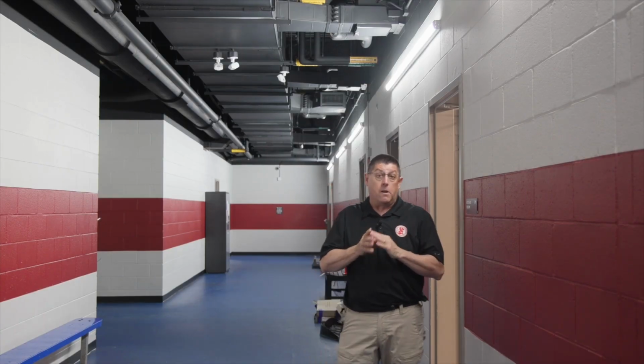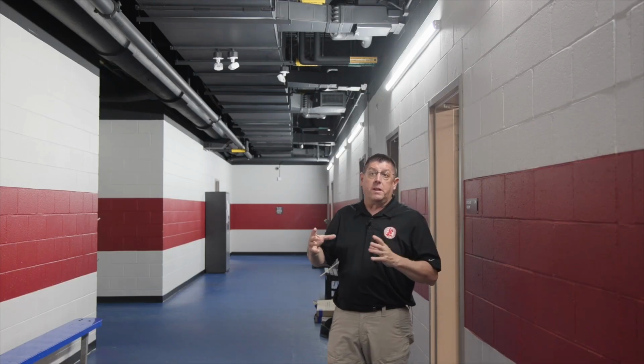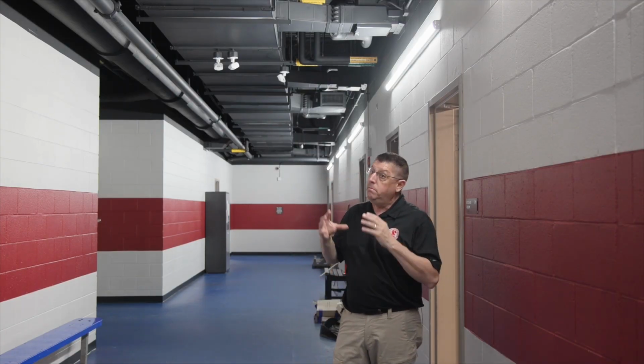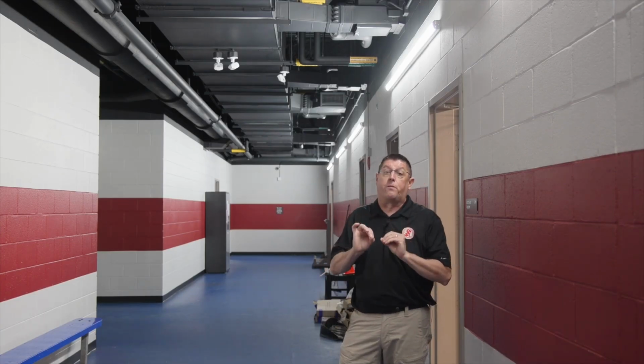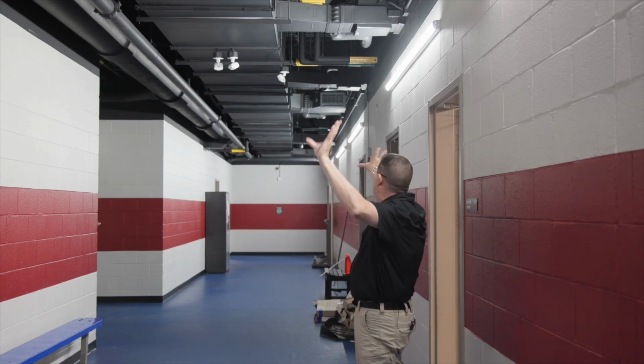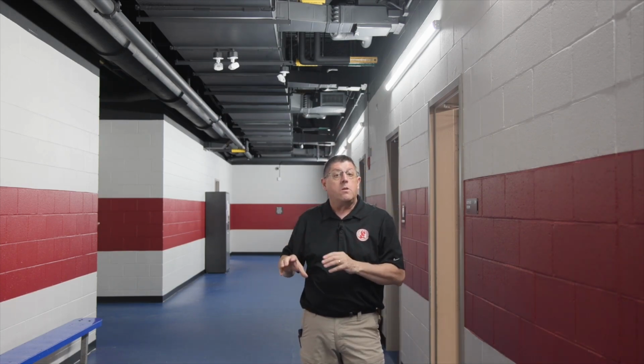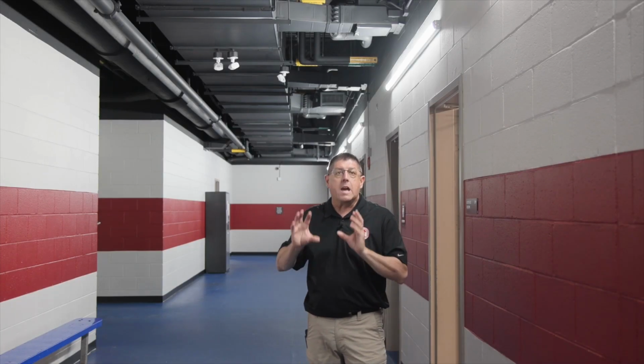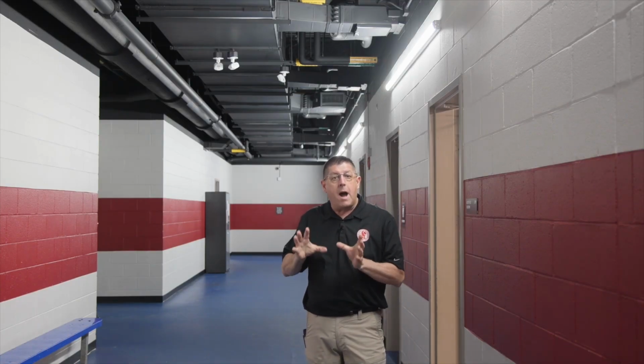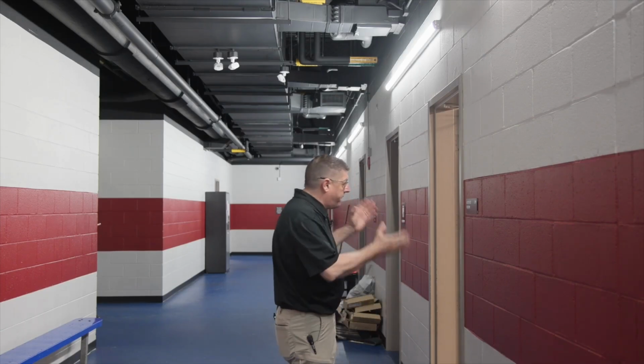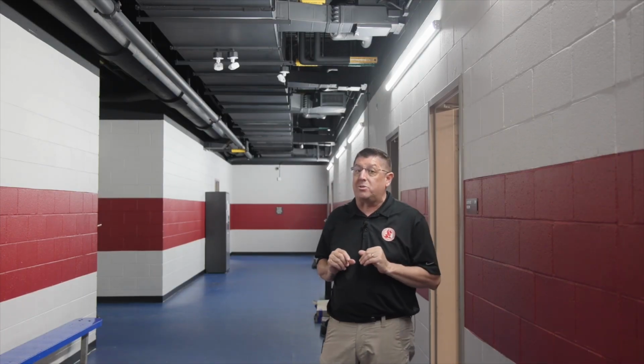In our particular case, if you think about commercial buildings, they are built for most high occupancy spaces. That means a lot of human element. So when we have a commercial building, we design them to be cooled first, heated second. So in our case, I've got air going through all of this ductwork from the chiller, the cooling tower, the air handler at a consistent cool temperature, 24/7, 365. But I can't throw 55-degree air into the locker room or into an office space or into any other space all year round and have any of the occupants happy at all.